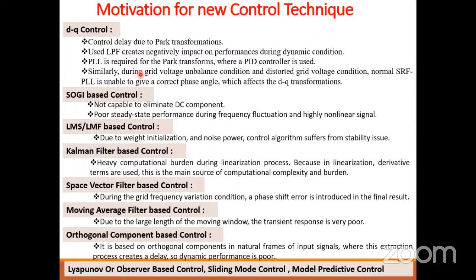The delay in the control network is a bigger challenge here, because this is an AC circuit, not a DC circuit—the signal is changing every moment. If you have a one-stage delay, meaning your estimation and your action have one step delay, then there will definitely be some error between what you estimated and what you actually face. So how do we overcome this? That is the challenge. Otherwise, these controls are very good for normal operations, but here we are going to sort out those issues.